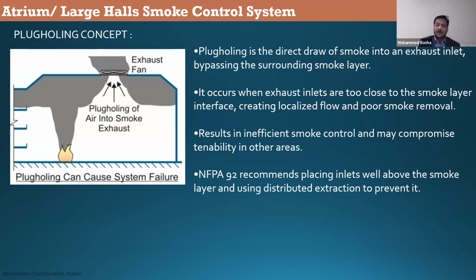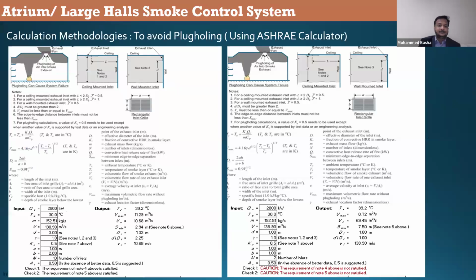You cannot just have one extract or two extracts, and even if the smoke extract size is a 4 meter square opening, this will not work properly. Let us see the concept. This is also again given by the ASHRAE calculator, but all of this we are going to see now in the analysis. Look at here. This is the inputs you need to provide.